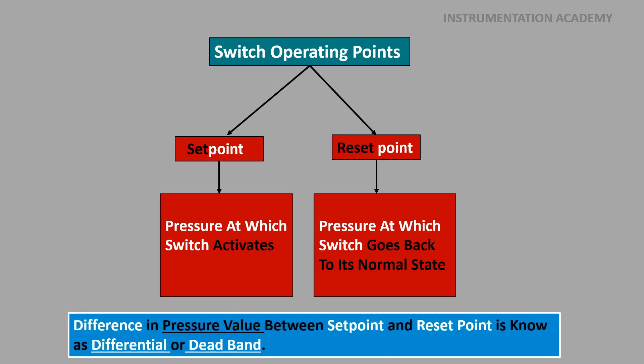The difference in pressure value between the set point and the reset point is known as differential or dead band of a pressure switch. In most switches differential can be adjusted, and some switches have fixed and non-adjustable differential.